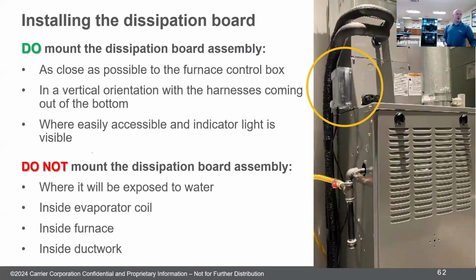So a question, can you bypass the dissipation board if the board sensor goes bad? That dissipation board is a safety device, just like a high pressure switch, low pressure switch, or high limit cutout on a furnace. No, it cannot be bypassed.